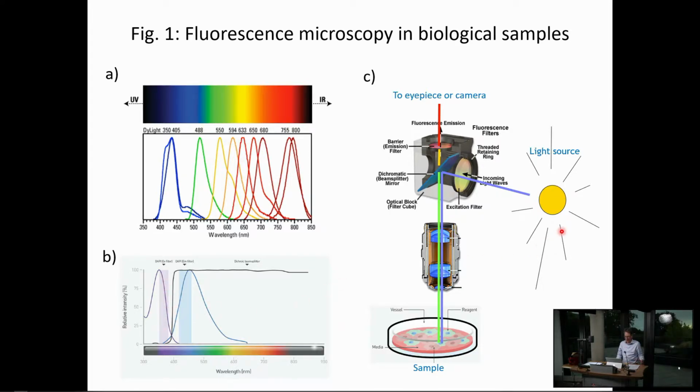And so you've already seen how you do that. So you may have your light source, then you have this excitation filter. We've seen this in the past. The excitation filter will pick out the color band that you want to excite the particular fluorophore you're interested in, pass that light down onto the sample. The fluorescence, the Stokes shifted light, passes through this dichroic beam splitter, so it's what's called a long pass filter.